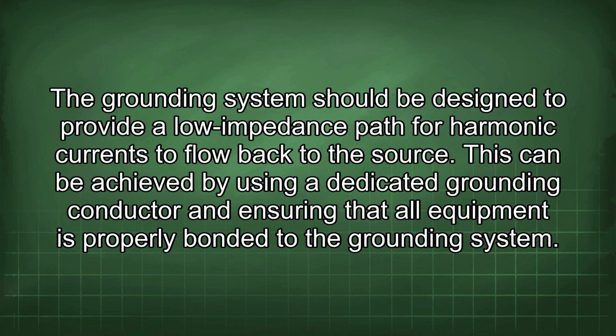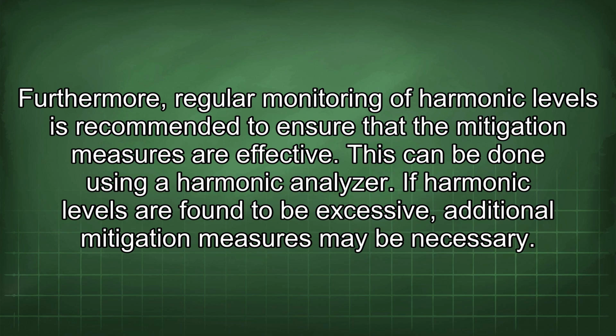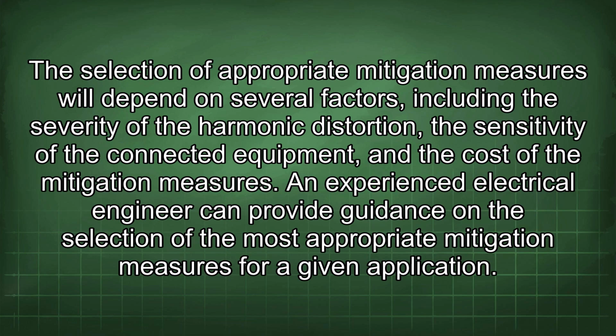the grounding system. Furthermore, regular monitoring of harmonic levels is recommended to ensure that the mitigation measures are effective. This can be done using a harmonic analyzer. If harmonic levels are found to be excessive, additional mitigation measures may be necessary. The selection of appropriate mitigation measures will depend on several factors, including the severity of the harmonic distortion, the sensitivity of the connected equipment, and the cost of the mitigation measures. An experienced electrical engineer can provide guidance in the selection of the most appropriate mitigation measures for a given application.